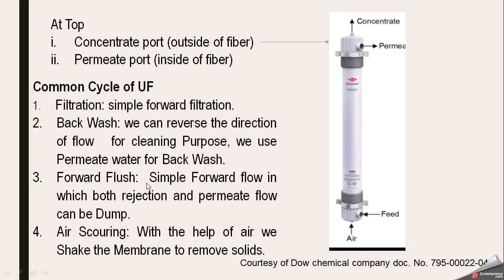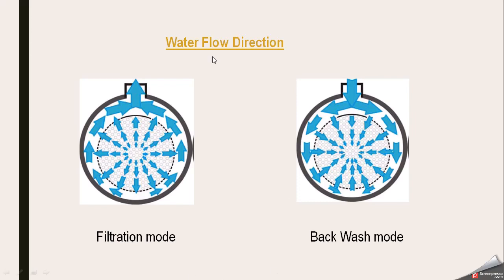Another way of operation is forward flush — simple forward flow in which both reject and permeate flow can be dumped; no resultant water is used. Then there is air scouring: with the help of air pressure entering the membrane, impurities stuck on the membrane surface are shaken loose and drop off, removing them from the surface.